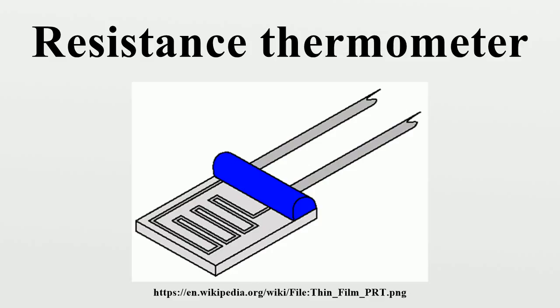Coiled elements have largely replaced wire wound elements in industry. This design has a wire coil which can expand freely over temperature, held in place by some mechanical support which lets the coil keep its shape. This strain-free design allows the sensing wire to expand and contract free of influence from other materials. In this respect it is similar to the SPRT, the primary standard upon which ITS 90 is based, while providing the durability necessary for industrial use.